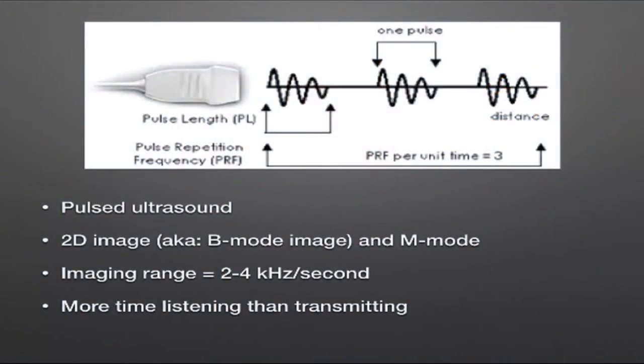Ultrasound images are made up from pulses rather than a continuous cycle. The ultrasound crystals send out one brief pulse into the body and then listen for reflections coming back. The sooner the reflection comes back, the closer that structure is to the transducer. These 2D images are also known as B-mode images, and there's another type called M-mode or motion mode. We send out around 2,000 to 4,000 pulses per second.